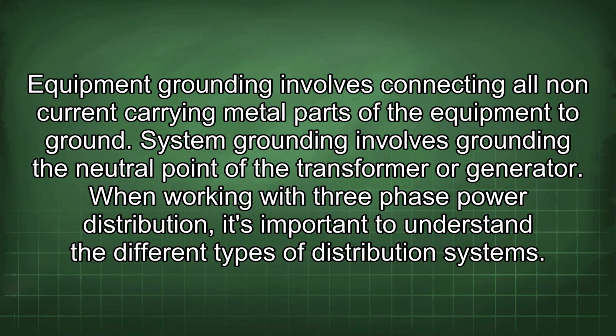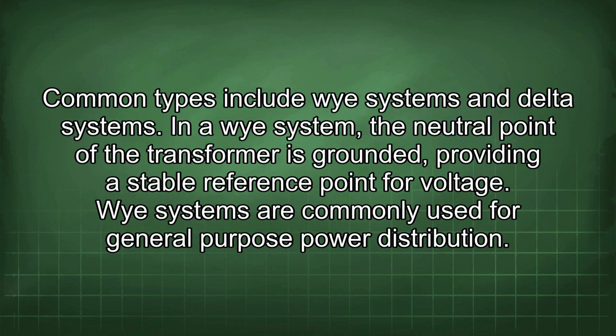When working with three-phase power distribution, it's important to understand the different types of distribution systems. Common types include Y systems and delta systems. In a Y system, the neutral point of the transformer is grounded, providing a stable reference point for voltage. Y systems are commonly used for general-purpose power distribution.